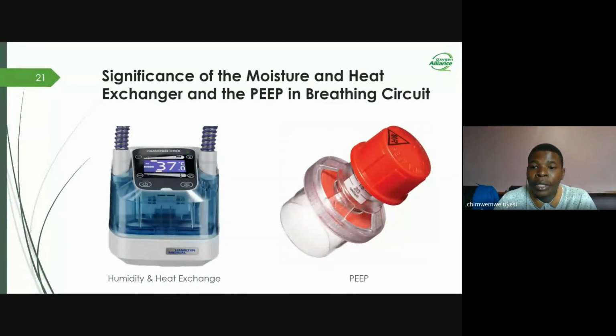In mechanical ventilation, when a patient is intubated, for example, the system bypasses the natural humidification mechanisms of the respiratory system. High flow rates coming from the ventilator itself can lead to the rapid drying and removal of moisture from the air pathways in the respiratory system. This happens especially at high flow rates, which results in dryness and also irritation of the respiratory mucosa. The humidification and heat exchange mechanism addresses these challenges by adding moisture and also conditioning the air.